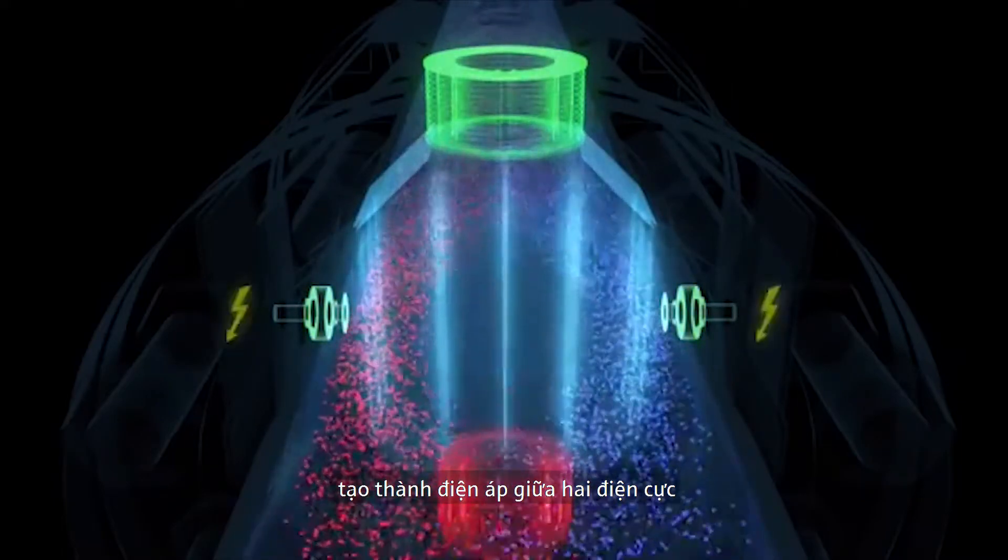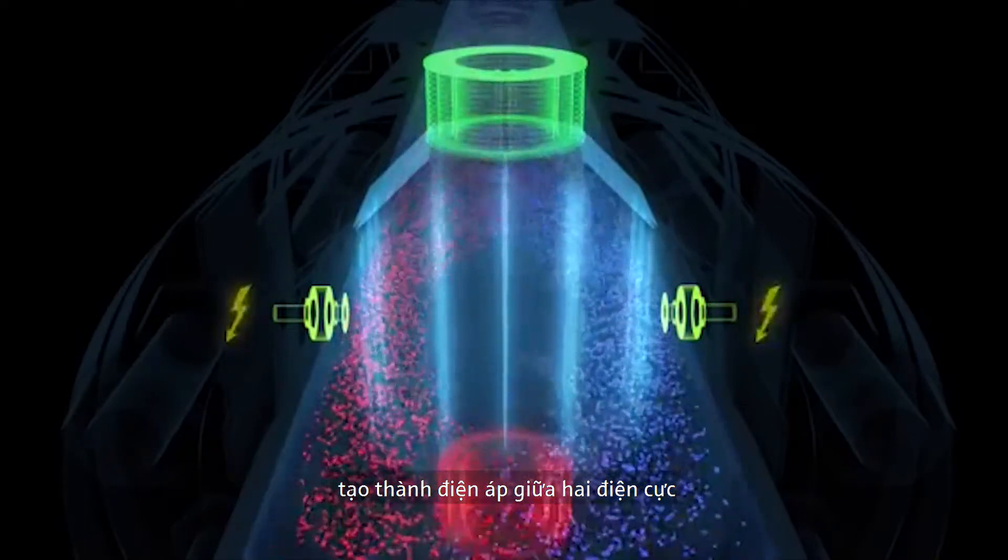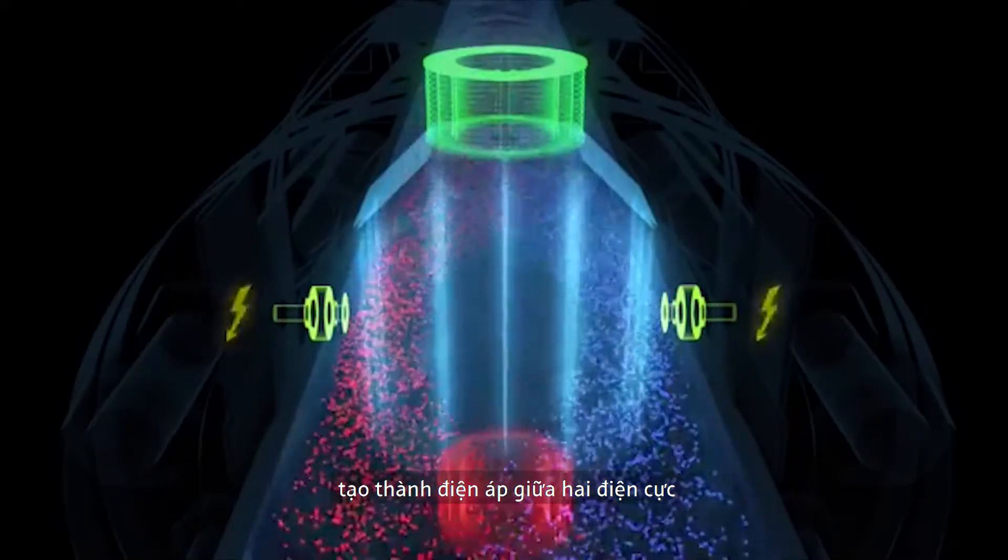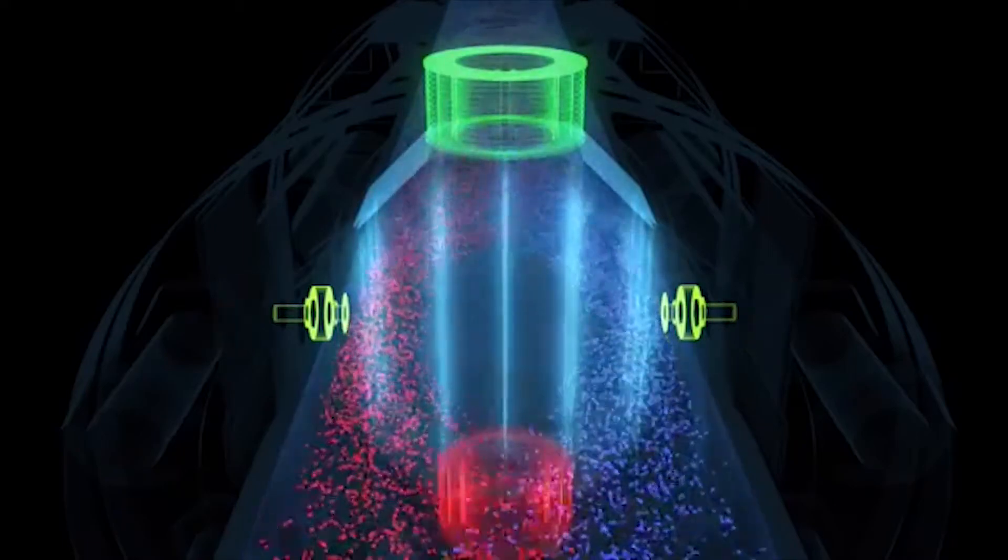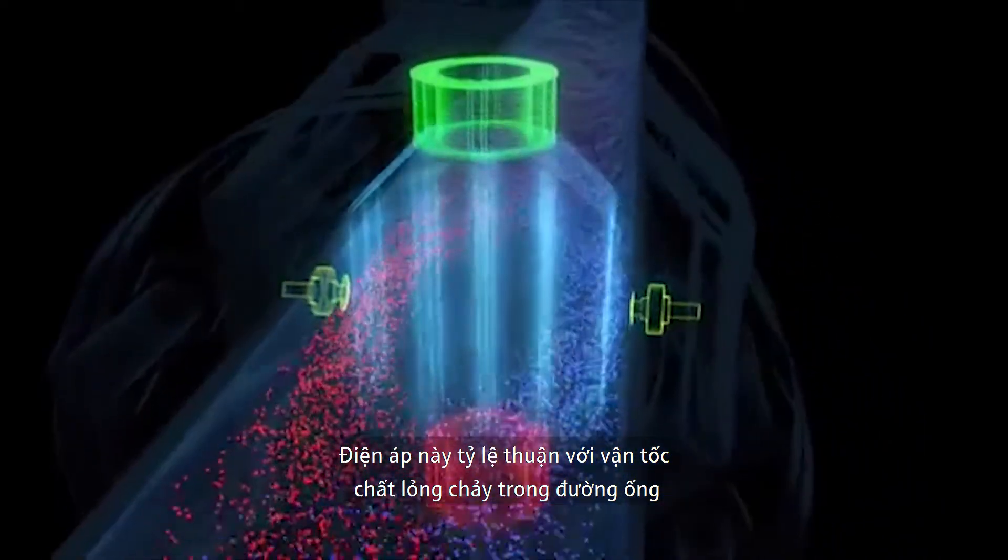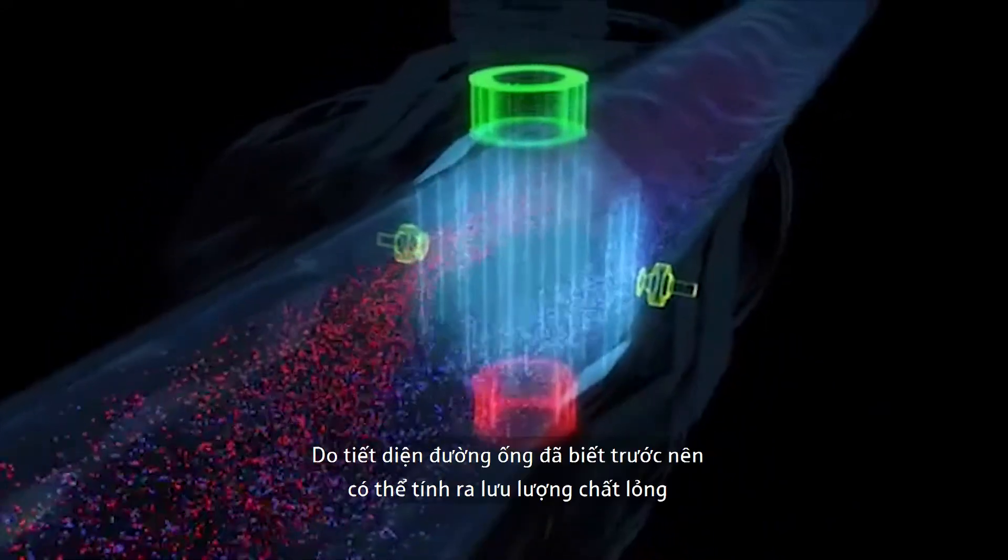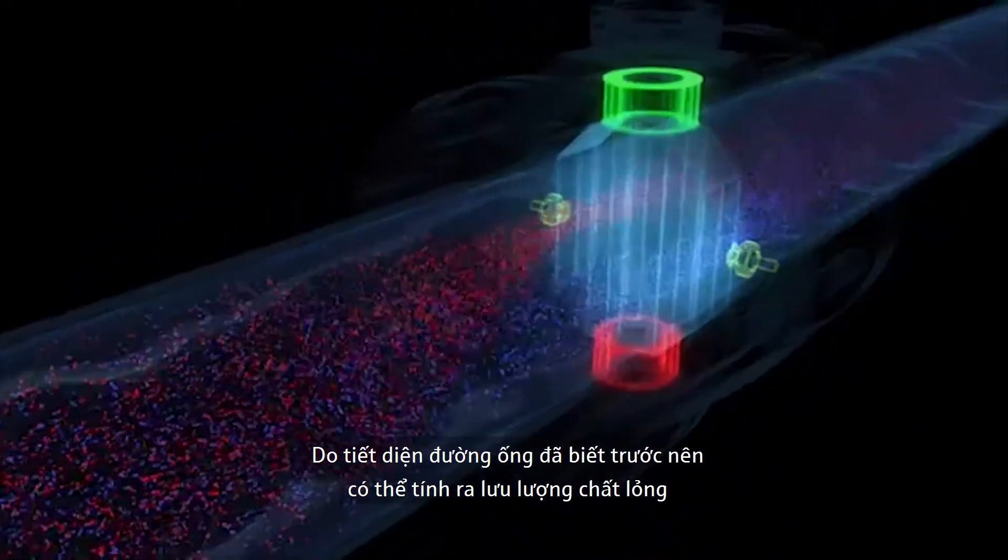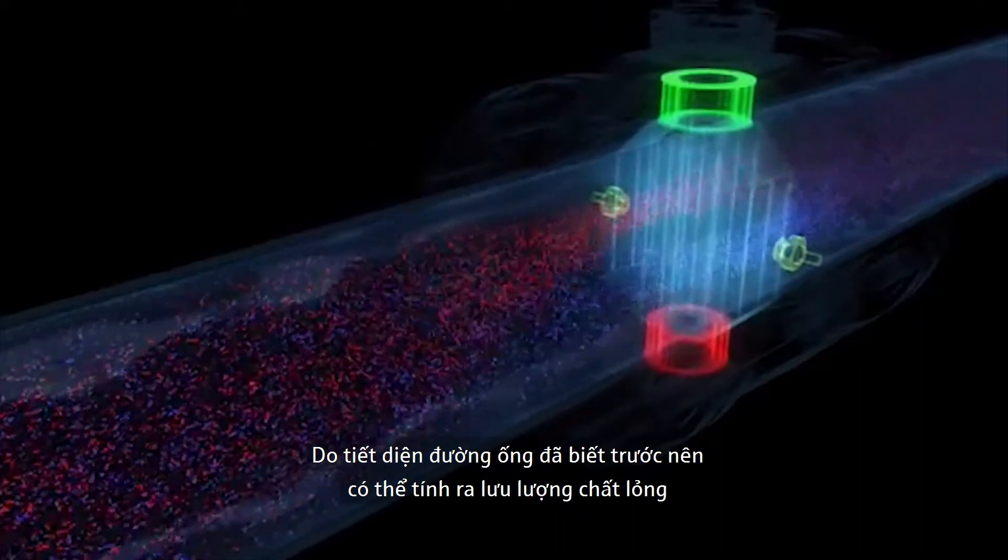Now an electrical voltage forms, which is detected and measured by the two electrodes. This voltage is directly proportional to the flow velocity in the pipeline. Together with the known tube cross section, the flow volume can be calculated.